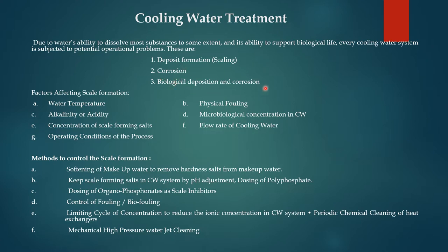Factors affecting scale formation are: water temperature, alkalinity or acidity, concentration of scale-forming salts, operating condition of the process, physical fouling, microbiological concentration in cooling water, and flow rate of the cooling water. These are all the factors affecting scale formation. The methods to control scale formation include softening the makeup water to remove hardness salts.